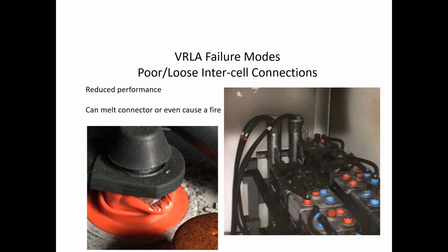None of these connections were torqued. So whatever installation group did the battery, it went under, say, a 700 amp load, 800 amp load. It's designed for like a 15-minute rate. This portion of the battery melted down and caused a fire, but all throughout the battery, all these connections had heated up and actually started to melt the post.